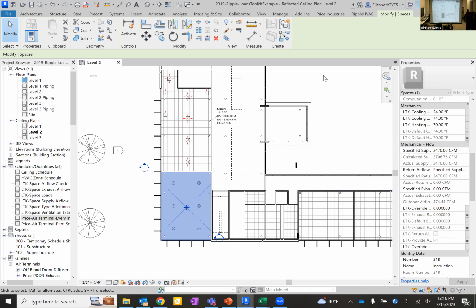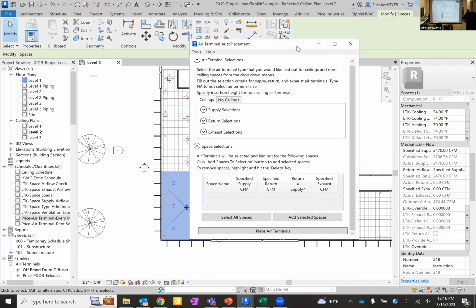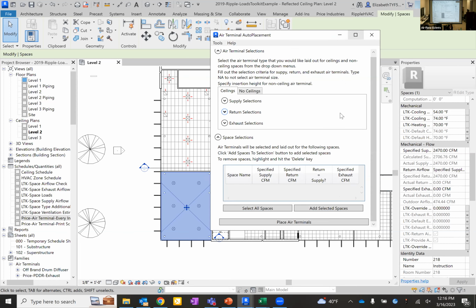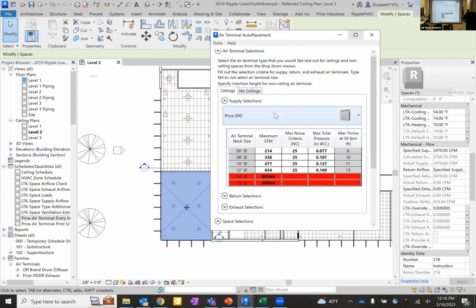Now, how is it sizing? You do have some control over the parameters there. So back in my little pop-out window from the Ripple plugin, I can set the parameters on how it's going to size all of my diffusers. For example, maybe company standard is that we don't size 6-inch necks above 180 CFM. I can set that, and now the program will only choose 6-inch necks at 180 CFM or less. Maybe sound sensitive project, we want to target 22 NC for all of the diffusers.